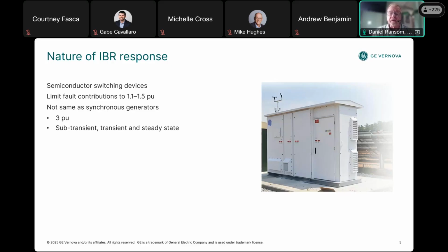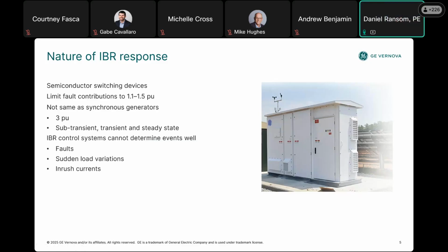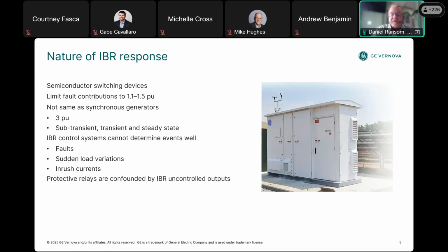These generators can go instantaneously to 300% and more for a period sufficiently long to allow the conventional protective relays to act. Additionally, IBRs do not go through the synchronous machine subtransient, transient, and steady state phases of a fault, but rather the IBRs up until now have operated in an inconsistent manner. So it's difficult for an IBR system to distinguish the difference between a fault and a sudden load variation or an inrush current. This unpredictable action confounds the relay coordination scheme.